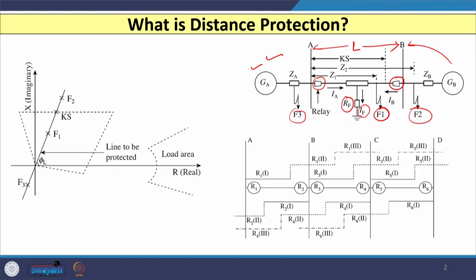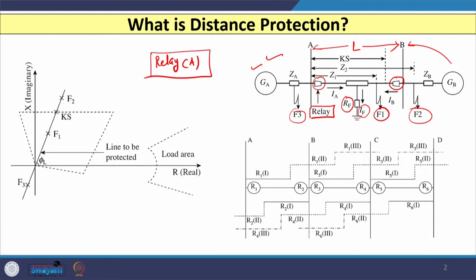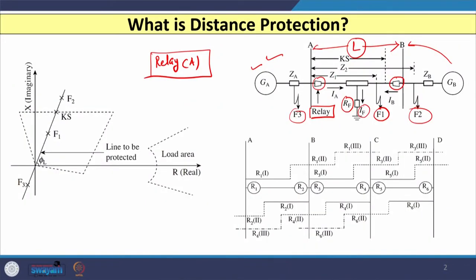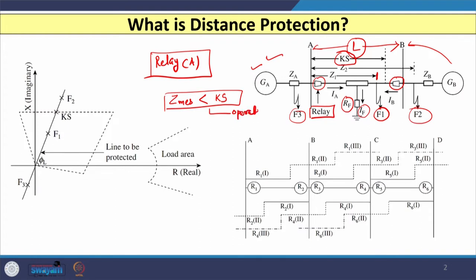Considering the relay located at substation A, the first zone of the distance relay is set at 80 percent of the line length L. If the measured value of impedance is less than the set value Ks, the relay operates; otherwise, relay blocks. This is the operating principle of the distance relay.